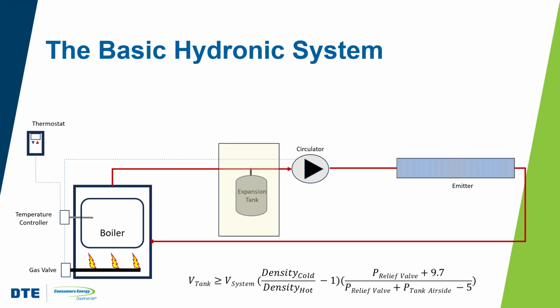So for the expansion tank itself, one side of it is a volume of air that is contained, right, in a diaphragm, and the other side of it is open to be able to accept the heated water that's expanded in volume, right? And so as the water enters the tank, the air volume gets depressed. Now, the way the tank is set up, no significant volume of water enters the tank until it's heated, right?